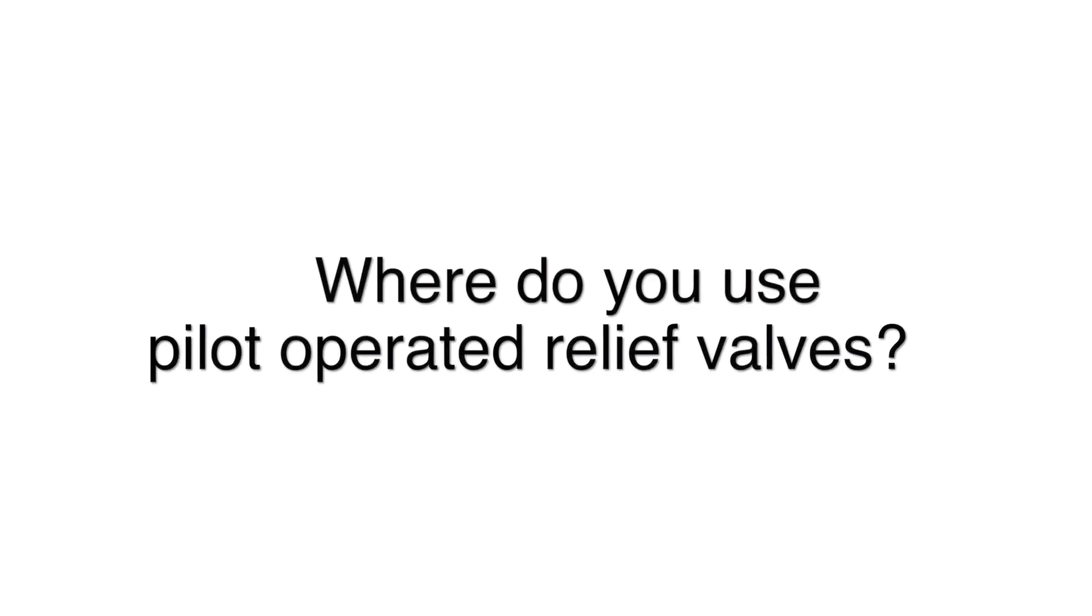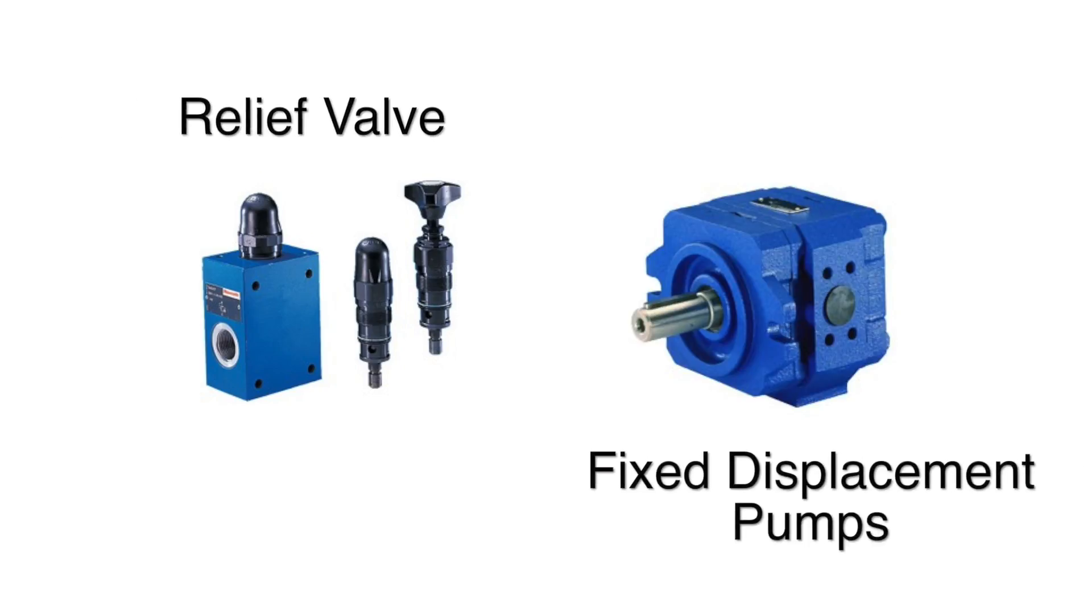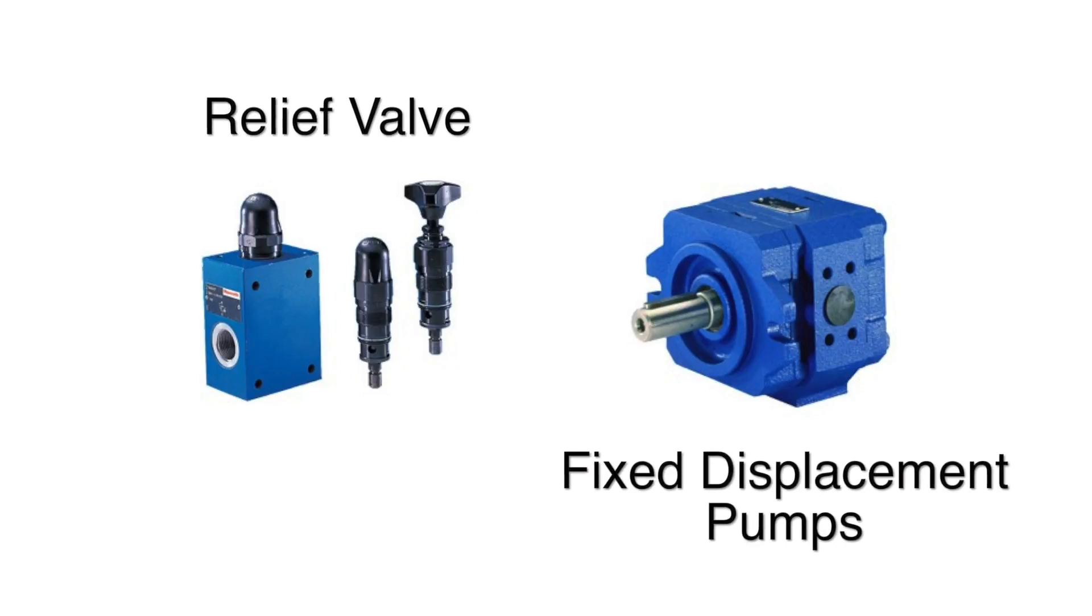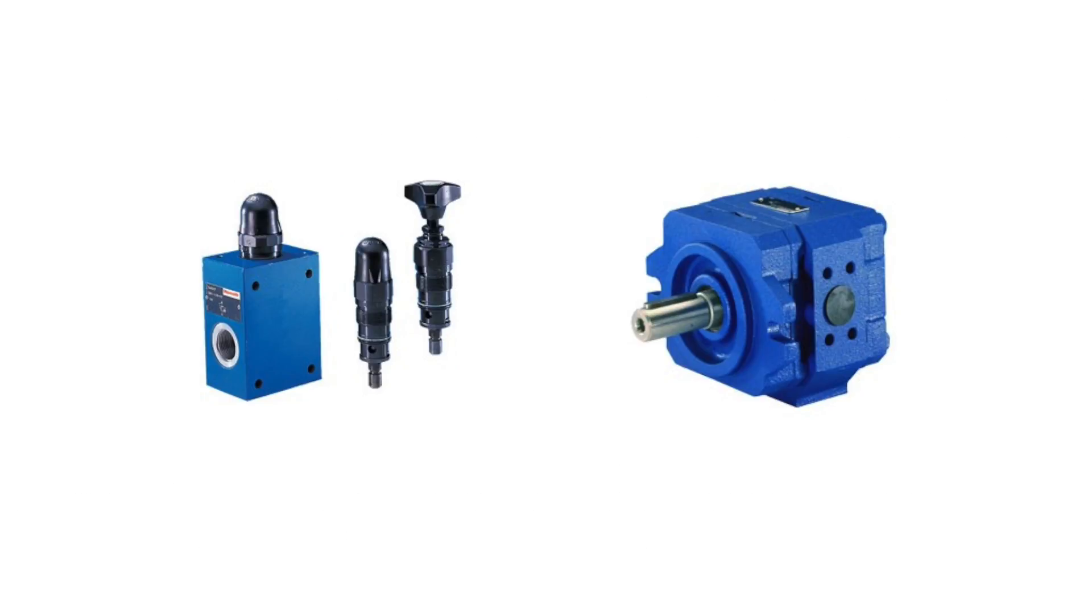Where would you apply a pilot operated valve? Any place where a flat pressure regulation curve is required. Relief valves in fixed displacement pumps are commonly of the pilot operated type. You could also use these valves in remote pressure control of a pressure compensated pump.